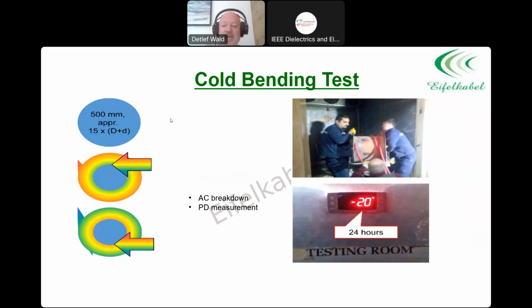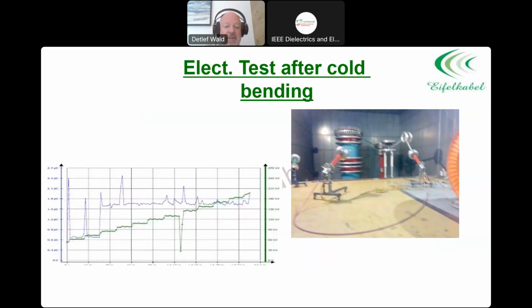However, as you can see here, these two nice guys, they made a test. So what we did, we put a cable around the drum, it's 15 times (D+d). We left it for 24 hours at minus 20 degrees, and then we unwound the cable, and afterwards we made an AC breakdown test and a partial discharge measurement, and none of these tests showed any significant damage to the cable. At minus 20 degrees, it was quite stiff, but we managed it so you can handle and install the cable at minus 20 degrees. So low temperature is not an issue.